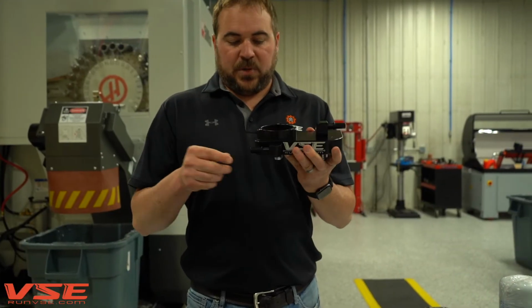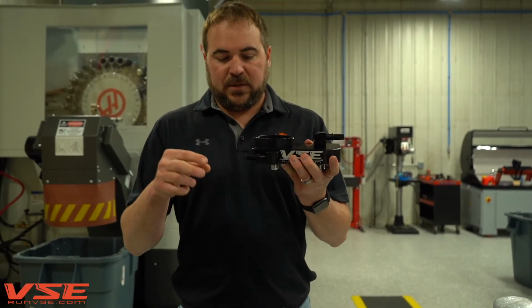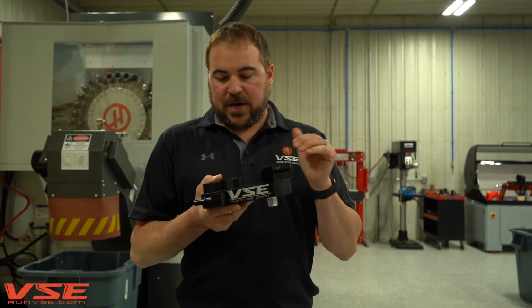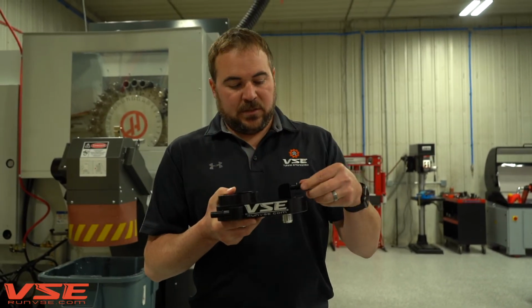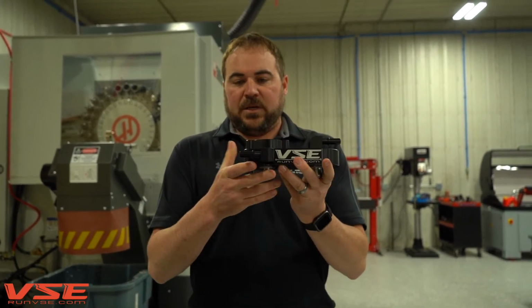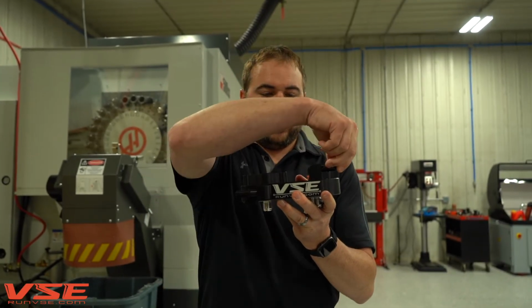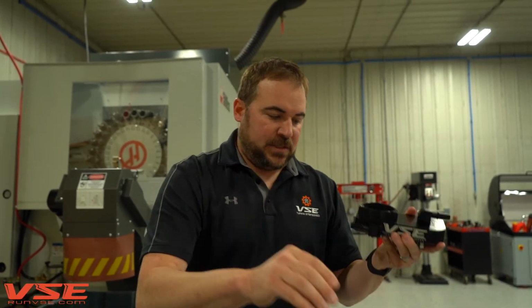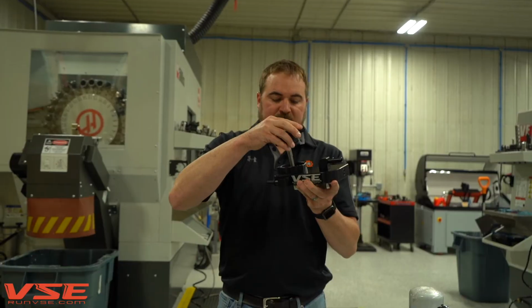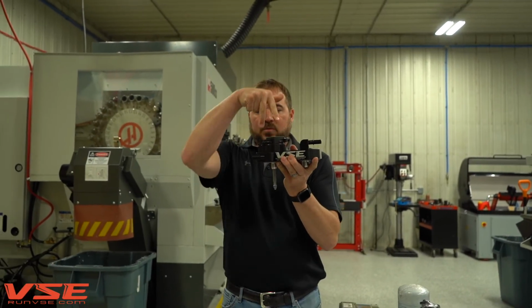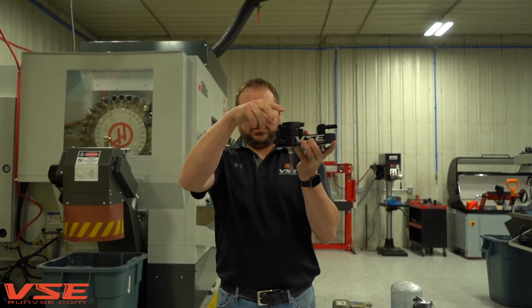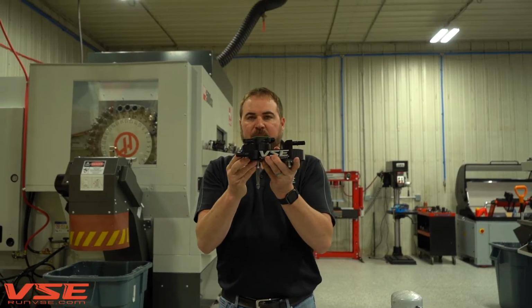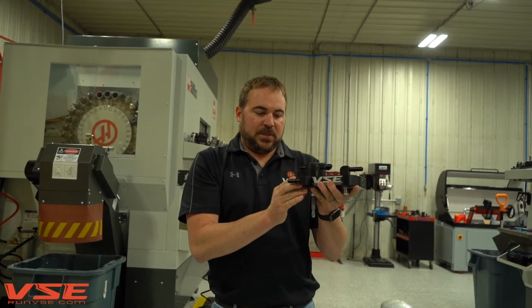These things are plug and play, so 17 and 19, these are 1/2 inch fittings that are port matched. You literally quick connect the factory fittings on this, bolt this guy in place, drop your conductivity sensor right down in there, run the screws that we supply, new O-rings for this, drop it right in place. It takes you about 30 minutes to install.